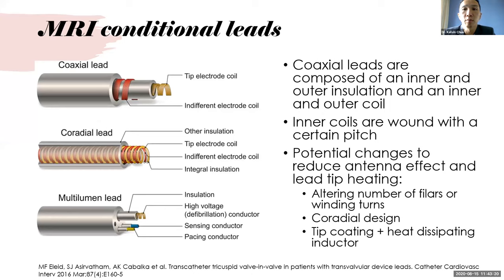Let's talk about the leads. Most pacing leads are coaxial in design. They have an inner and outer insulation and an inner and outer coil, delivering strength while maintaining flexibility and durability. The inner coils are wound three-dimensionally with a certain pitch or angle. Changing the geometry of this relationship by altering the number of filars or winding turns can change the propensity of the lead to act as an antenna or the likelihood of efficient lead tip heating.